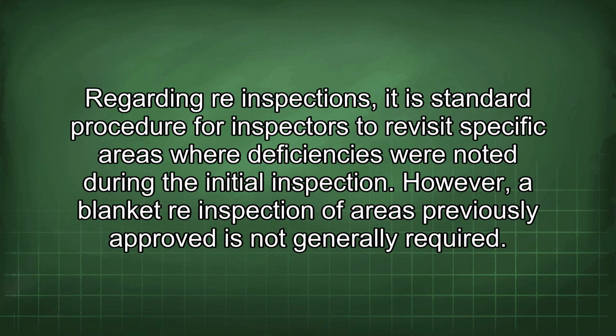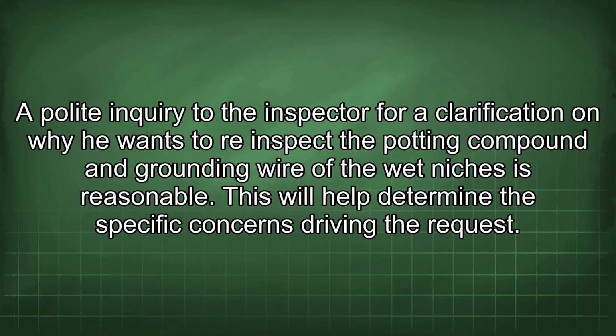Regarding re-inspections, it is standard procedure for inspectors to revisit specific areas where deficiencies were noted during the initial inspection. However, a blanket re-inspection of areas previously approved is not generally required. A polite inquiry to the inspector for clarification on why he wants to re-inspect the potting compound and grounding wire of the wet niches is reasonable. This will help determine the specific concerns driving the request.